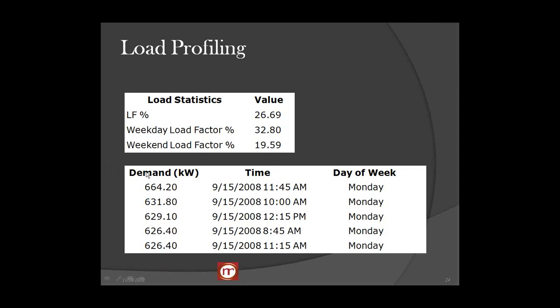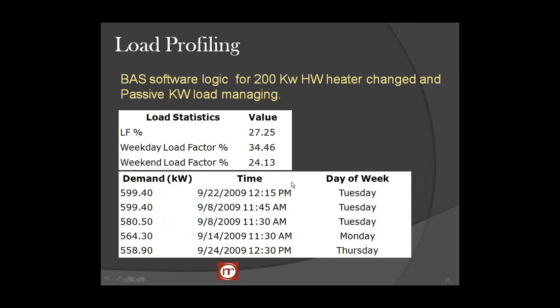In 2008, you can see that this had a max demand for that month of 664 kW and a load factor of about 32% during the week. What's important here is the 664. That's what we're paying at $10.10 a kW. So that was with the energy program with no load shedding. Now, in 2009, a year later, we are down to 599.40 kW. That's a 65 kW reduction.